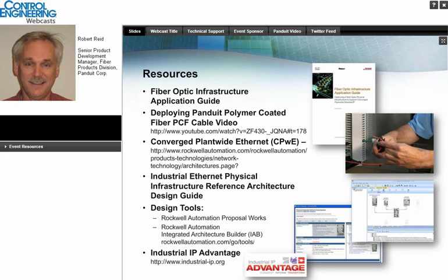I would say that a high-value link, being a fiber backbone where I'm going out to a TE, as an example, that serves many devices, like an island of automation, a high-value link that might be reconfigured or patched inside of a TE, would be a good application for patching. And I did show earlier a DIN rail-mounted patch facility where you can take that backbone cabling in, and you've got a patch facility for all the fibers on the panel of that enclosure.